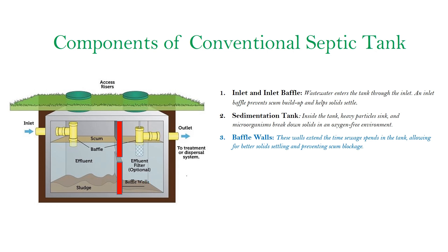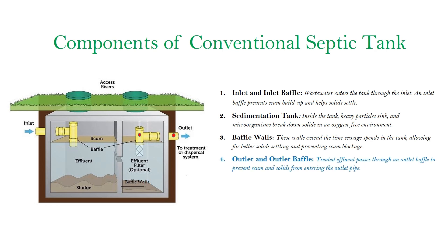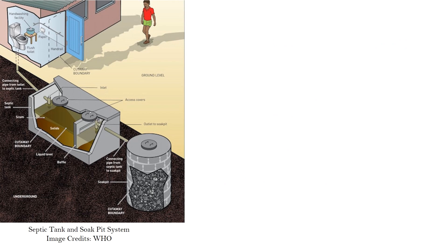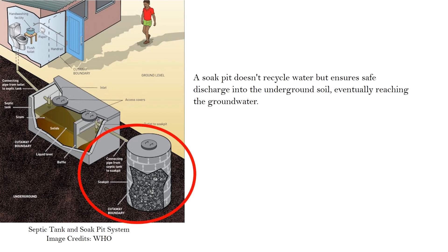Fourth, the outlet pipe and outlet baffle: treated effluent passes through an outlet baffle to prevent scum and solids from entering the outlet pipe. Fifth, the soak pit or drainage field: the final treated effluent goes to a soak pit or drainage field, where additional purification occurs before it reaches the groundwater. A soak pit doesn't recycle water but ensures safe discharge into the underground soil, eventually reaching the groundwater.